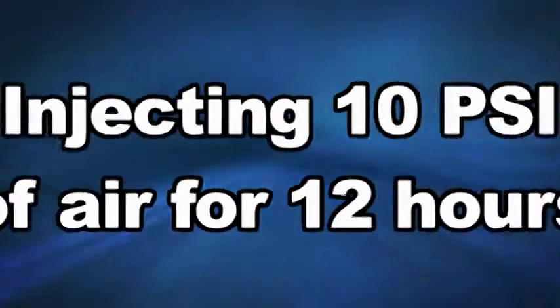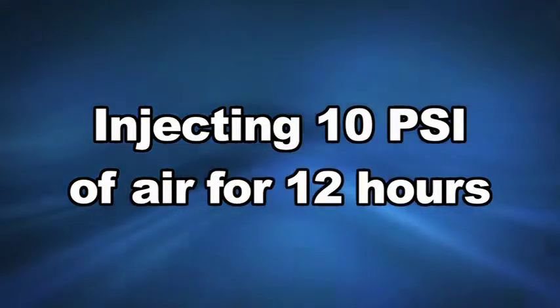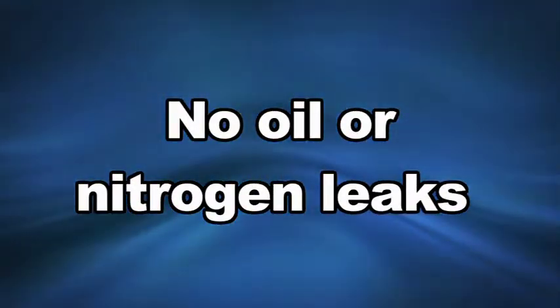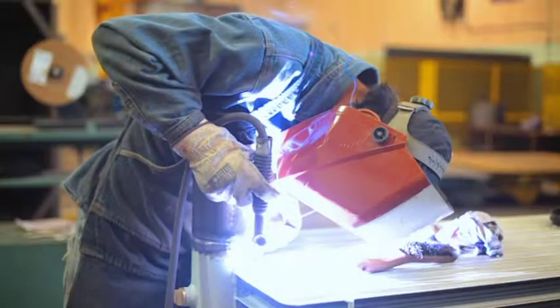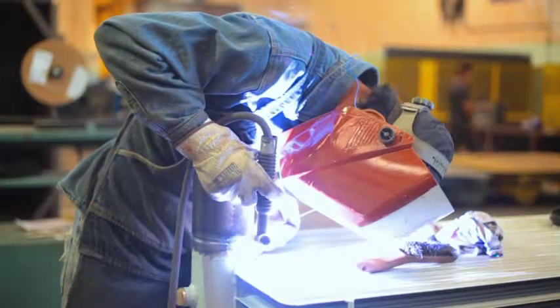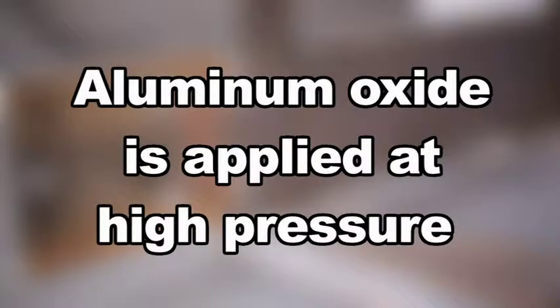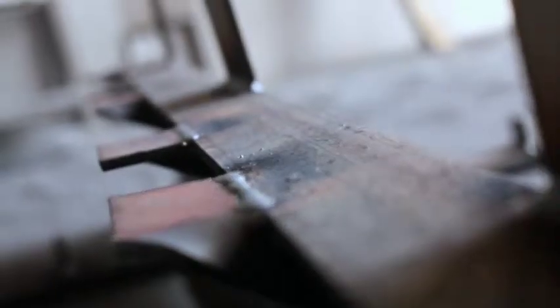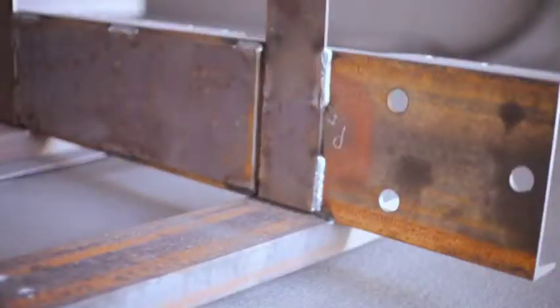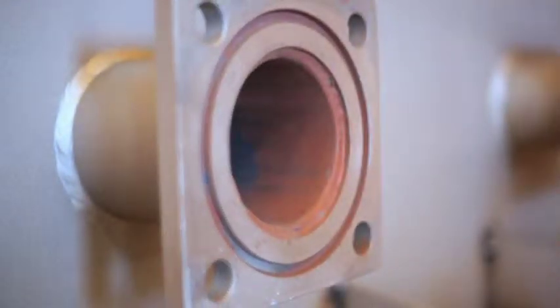This is accomplished by injecting 10 psi of air for 12 hours to ensure there will be no oil or nitrogen leaks during the operation of the transformer. Once past this quality test, the tank is sent to our sandblast booth, where aluminum oxide is applied at high pressure to remove any impurities that might be deposited on the metal and create an appropriate anchor with a metal finish suitable for the base primer, which will be applied in the following process.